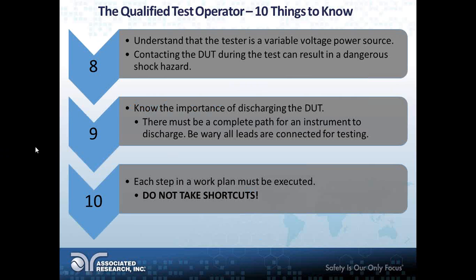Understand that a tester is a variable voltage power source. Even though the hipot tester is high voltage, lower current, it's still a variable voltage power source. Contacting a device under test during the test results in a dangerous shock hazard. I think that kind of goes without saying with everything we've been talking about here. Know the importance of discharging your DUT. There must be a complete path for an instrument discharge. Be wary all leads are connected, and that's something I just mentioned. Yes, all of our testers will automatically discharge, but only if the leads are attached. If somebody knocks off the return lead in the middle of a test, all you're doing is charging that thing up. And if somebody goes and touches it, they are going to get hit. The unit can't discharge if there isn't a complete path.